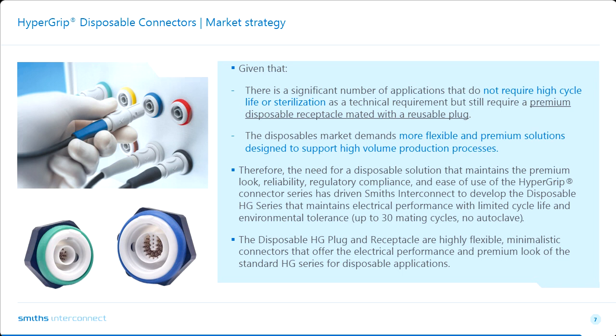and environmental tolerance. When you say disposable, it sounds like you only connect it one time. Typically, even a disposable throughout the time of a procedure is mated and demated a few times. So we rate it up to 30 cycles, so that even if it's mated and demated 5, 10, 15 times within a procedure, there's no risk of it failing. The disposable HG plug and receptacle are highly flexible, minimalistic connectors that offer electrical performance and premium look of the standard HG series for disposable applications.